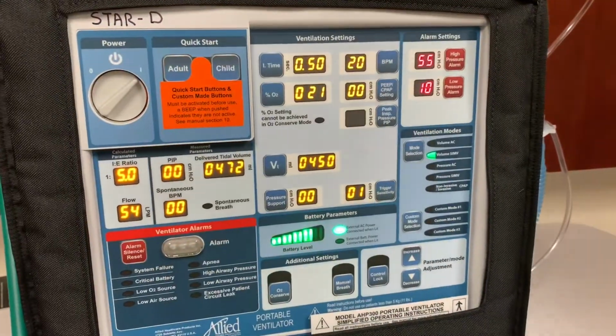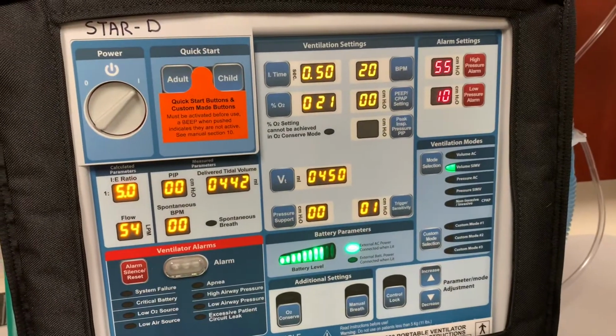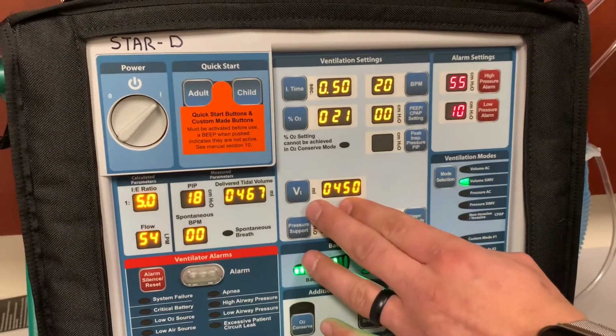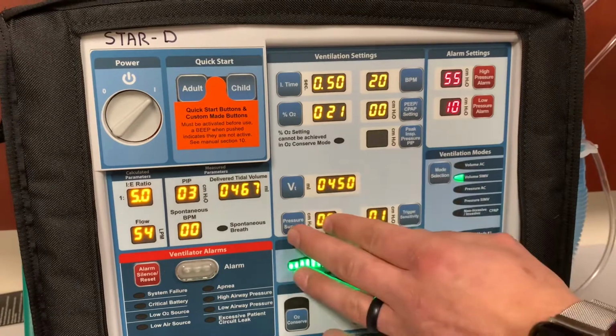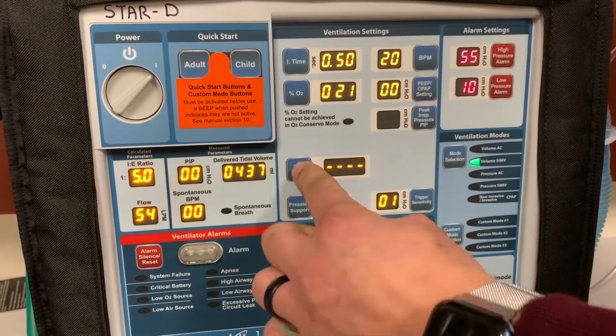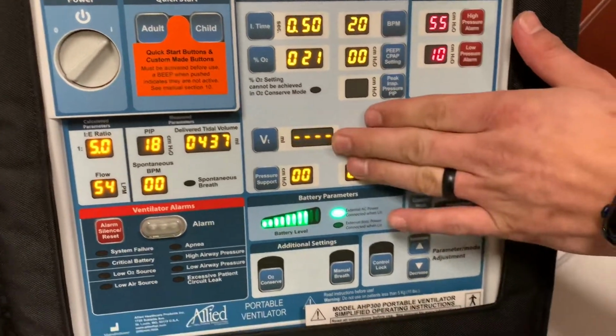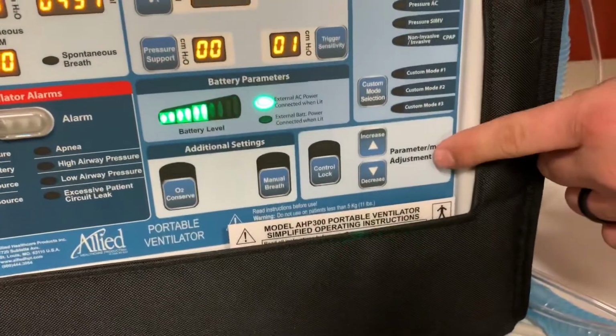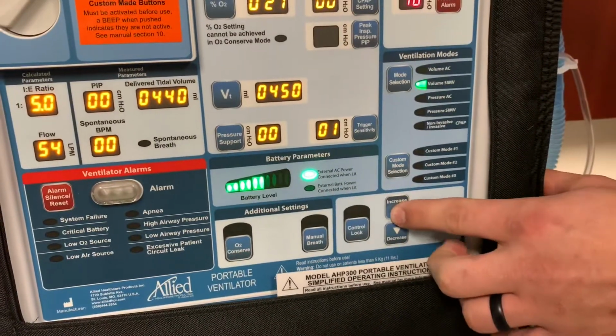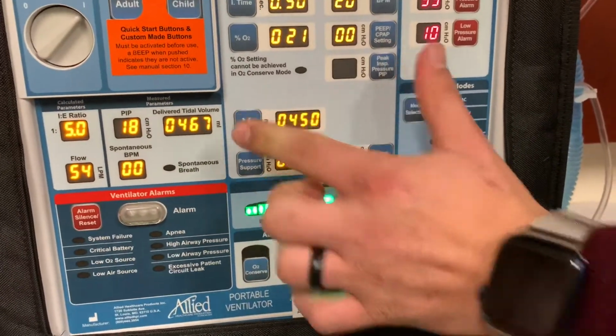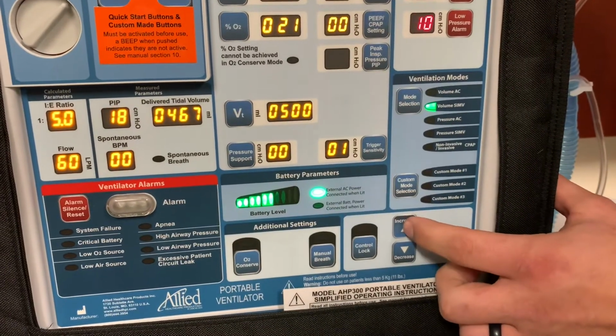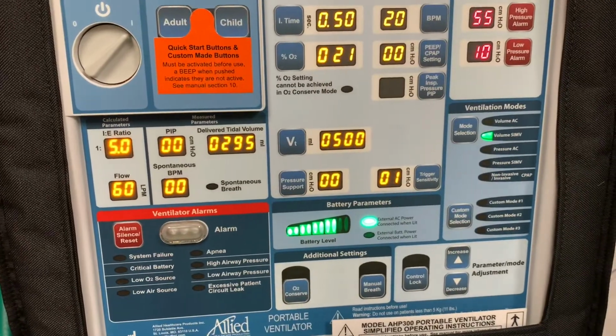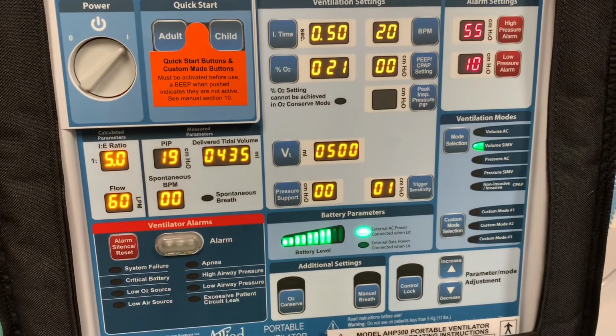Any setting that you wish to change, ranging from breaths per minute or tidal volume or any other inspiratory time or oxygen percentage, simply select the area that you want. It will begin flashing, and you can adjust using the increase and decrease button. In this case, we're going to increase the tidal volume to 500. Simply hit again. It will stop flashing and it locks in.